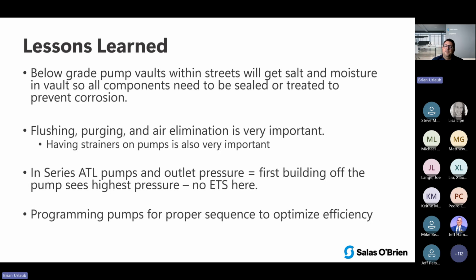All right. In these ambient loop systems, if you're going to do multiple in-series pumping, what we learned here is that the first connection or takeoff out of the pump vault is going to see the highest pressure, obviously. Well, some of those residential homes, because there's no energy transfer station, they were seeing 150 psi at the heat pump, which is borderline what we want to see with the piping and the hose kits, et cetera, and the materials that were used on that project. So you really have to pay attention to your pressures.